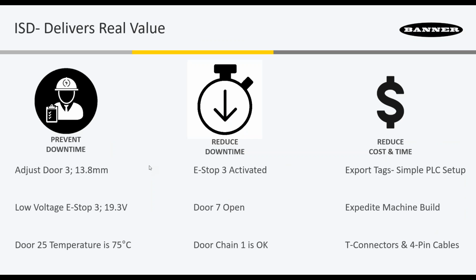And the advantages of that, reducing downtime is something that you could do before, but now we're doing it with simplified wiring. So I can tell you what E-stop was pressed, where it is, what door is open, I can tell you some information about the entire chain. But preventing downtime, this is pretty amazing, because what we can do is, since we're talking from a sensor to the PLC, we can let you know when the door is just at the edge. We're starting to sag, it's still closed, but if it goes any further, it's going to be open. So you can go make an adjustment to the door before it causes downtime. We can alert you if there's a low voltage issue, so maybe there's a power supply problem or wiring issue, and send an alert based on that. It even tells you temperature of the sensor. It has a lot of very good information to help prevent downtime.